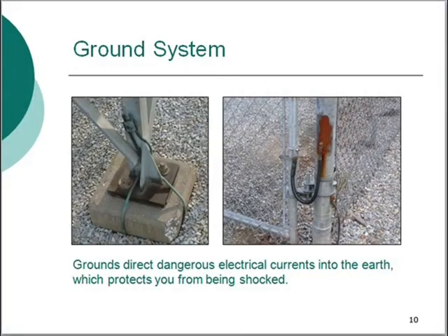Substation fencing, structures, and equipment are grounded, which is to say, they are connected to a wire mesh grid buried 24 inches below subgrade. In the event of a lightning strike or equipment failure, the grounds direct dangerous electric currents into the earth, which protects you from being shocked. Prior to entering a substation, be sure to check the gate and fencing to verify grounds are in place. There should be a ground from the gate post into the earth, and a flexible strap between the post and gate. Unfortunately, the theft of station grounds is occurring with increased frequency. If you find damaged or missing grounds, do not touch the fencing or equipment. Report problems to the Transmission or Distribution Dispatch Center.